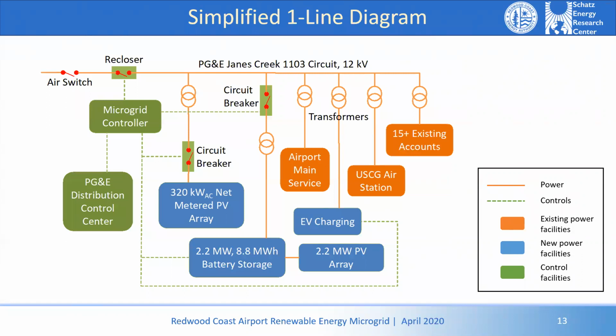And then you also see the green recloser and circuit breaker. So if I start up in the upper left-hand corner with the recloser, that is an automated switch that's being installed. And as I mentioned a minute ago, when the main grid, bulk grid goes down, that recloser will open and will isolate the microgrid. And then the generation on the microgrid will form an island and support the loads on the microgrid. You can see there's a microgrid controller there that has control over the recloser. It also has control of the circuit breakers that are shown. Those are SCADA controlled circuit breakers, basically automated controlled circuit breakers. There's also control from that microgrid controller of the generation and the EV charging. That microgrid controller is actually multiple controllers. There are actually 2 controllers, and that was a design decision that was figured out early on in the project.